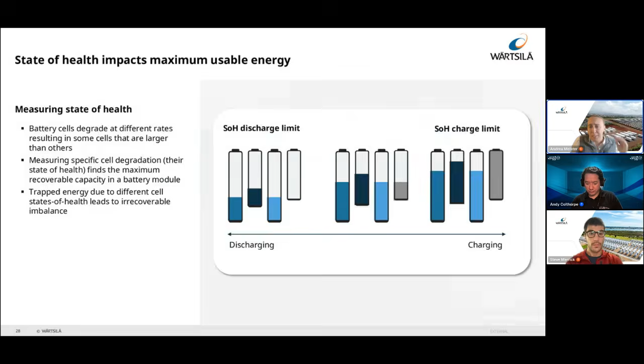So a quick preview of what we might see in a battery analytics tool: here's a screenshot from Pulse. That top line is our maximum total capacity. Between the top line and the next line down, that's your cell imbalance - that's potentially recoverable capacity. This screenshot is from a really healthy site, where the imbalance hovers at about 1%.